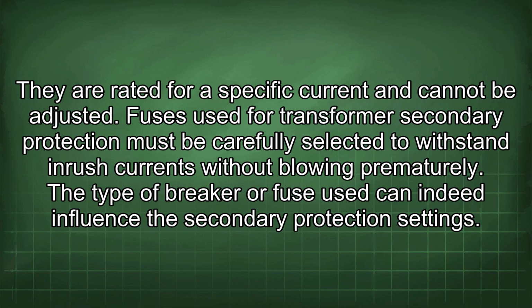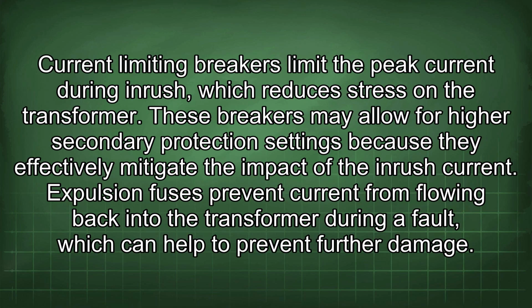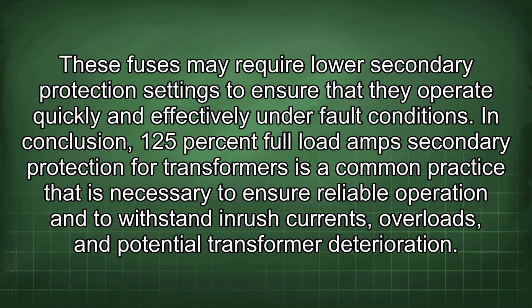The type of breaker or fuse used can indeed influence the secondary protection settings. Current limiting breakers limit the peak current during inrush, which reduces stress on the transformer. These breakers may allow for higher secondary protection settings because they effectively mitigate the impact of the inrush current. Expulsion fuses prevent current from flowing back into the transformer during a fault, which can help to prevent further damage. These fuses may require lower secondary protection settings to ensure that they operate quickly and effectively under fault conditions.